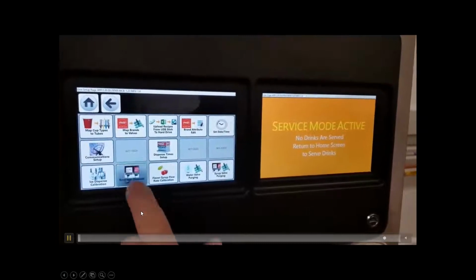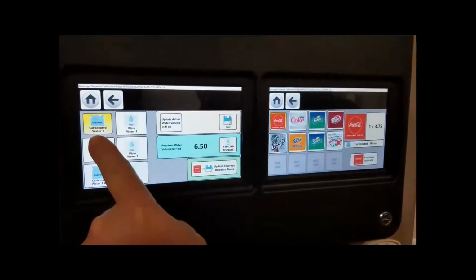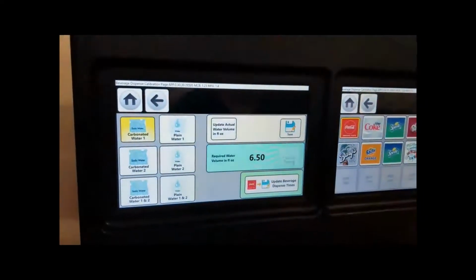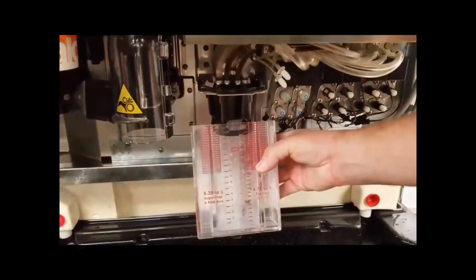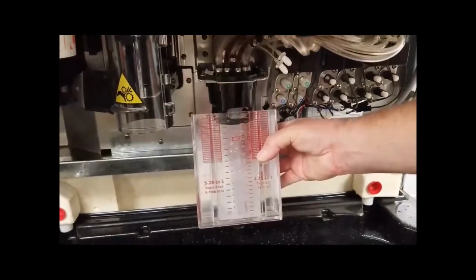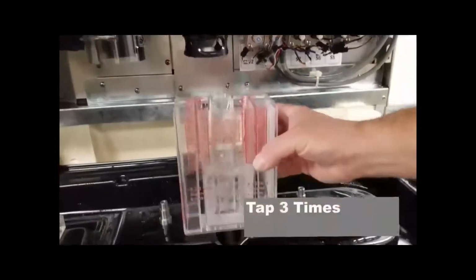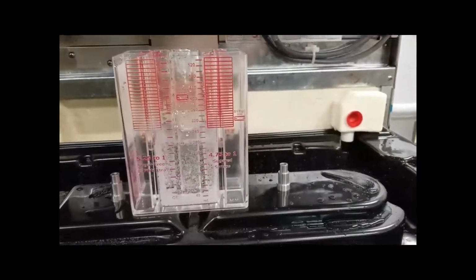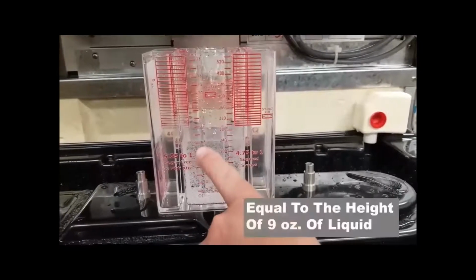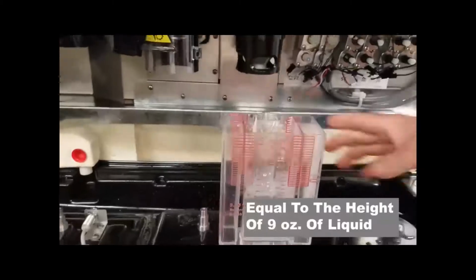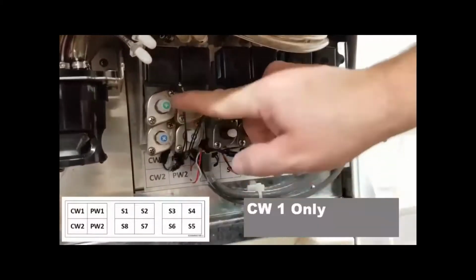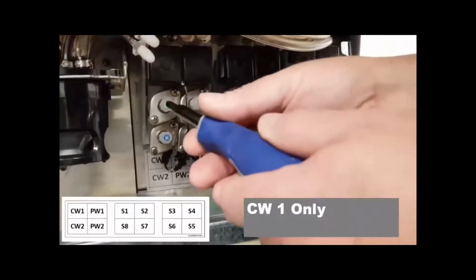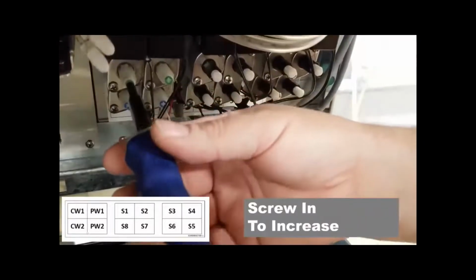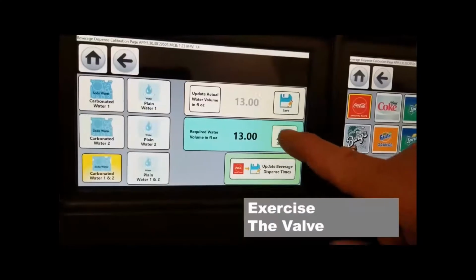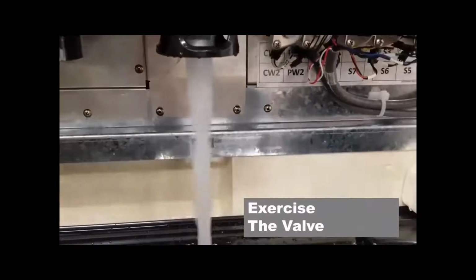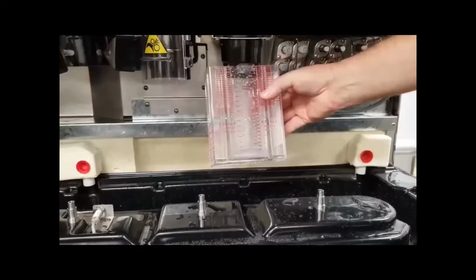So to set up our calibrations for water, we're going to proceed with going back into the beverage dispense calibration screen in technician mode through unit setup. And what we're going to do is set our highs to 9 ounces. So carbonated water 1, which is our high, will be set to 9 ounces, which is CW1, as you can see here. And we're going to adjust that using our top flow control, which is green. Remember, green is high. You do a 4-second dispense, and you go and get your reading once again.